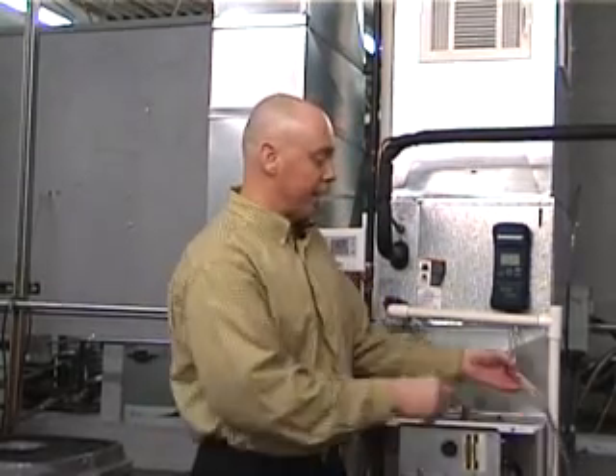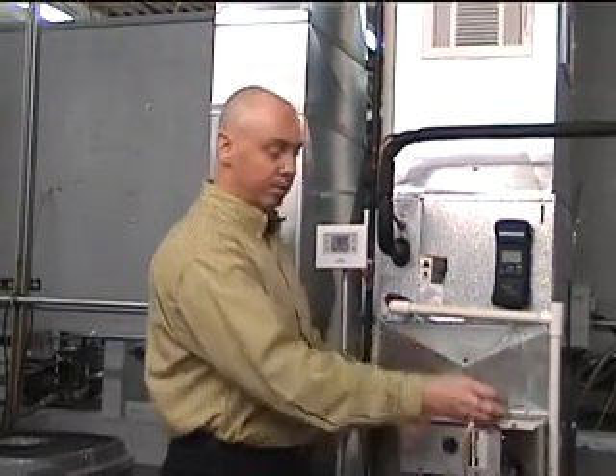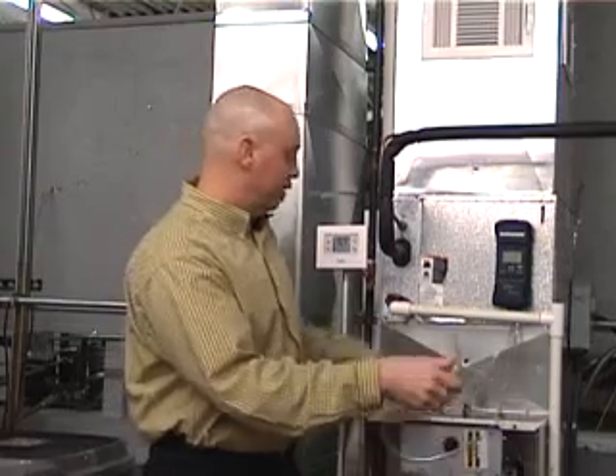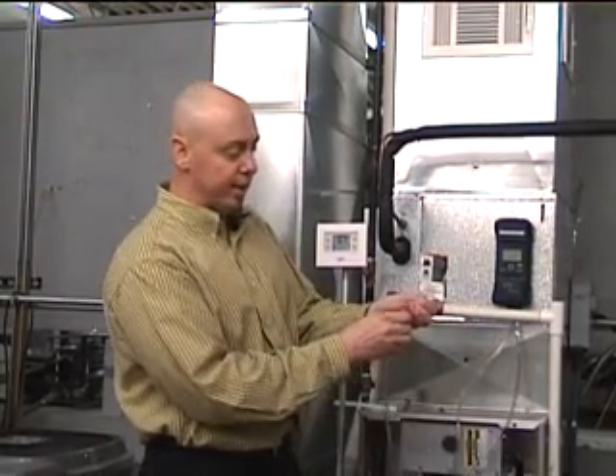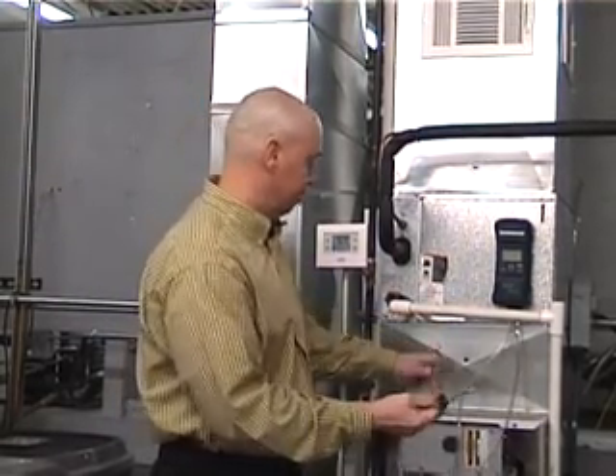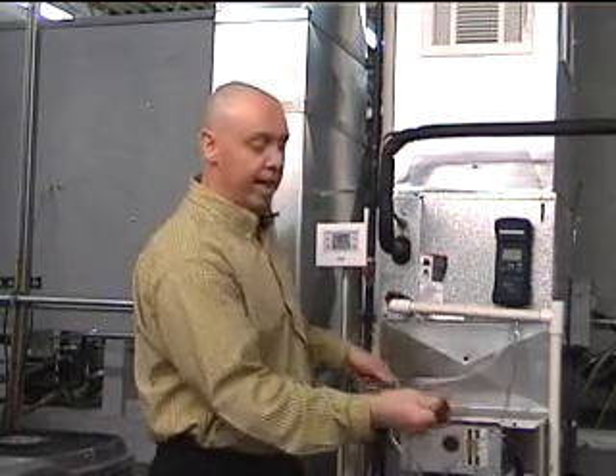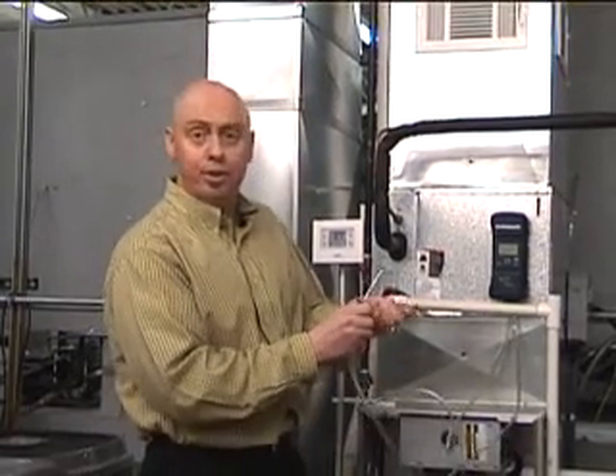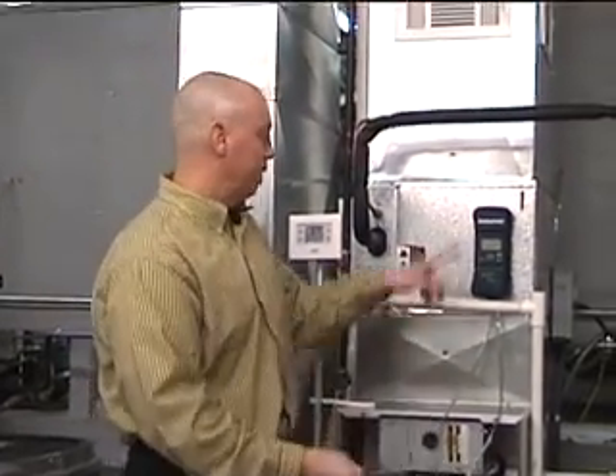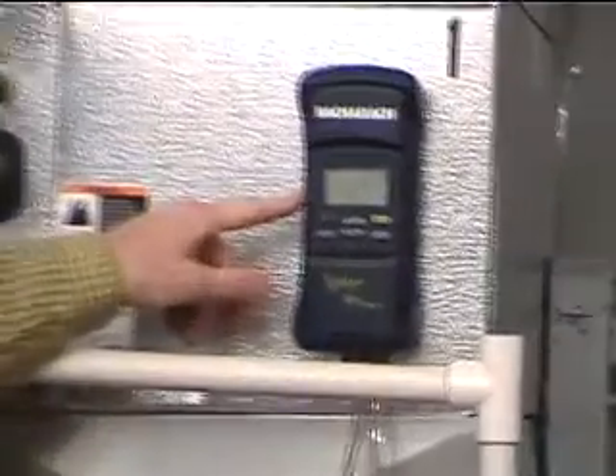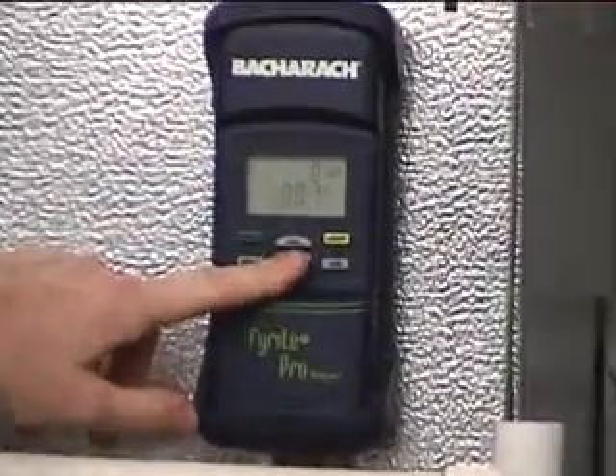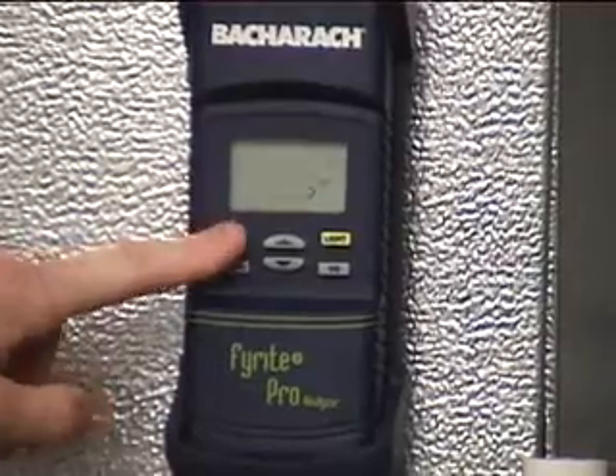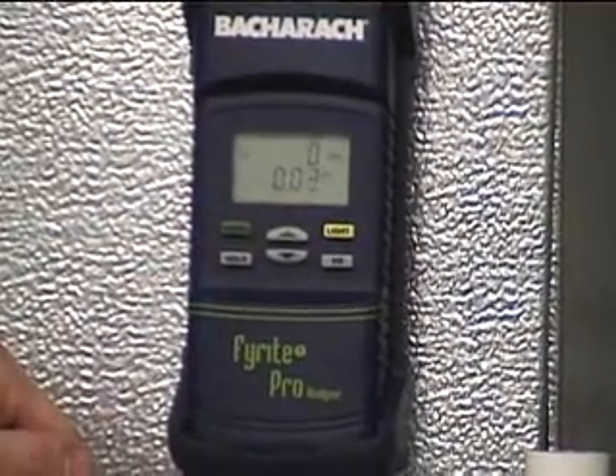What I did is I have the Fyrite Pro running as a manometer. I have two hoses. I'm running it as a dual manometer. So I take my static probes and I attach them to the end of the hoses. And before I insert my probes into the duct system, I want to zero out the meter. One way I can zero out the meter here is I scroll down and then I hit the enter button and it should zero the meter out.